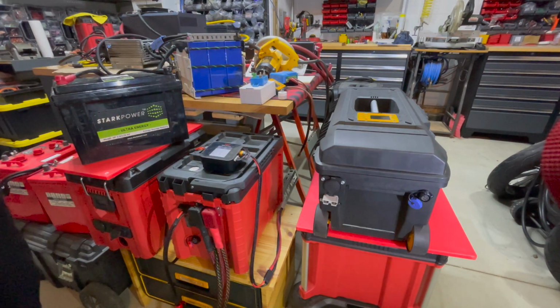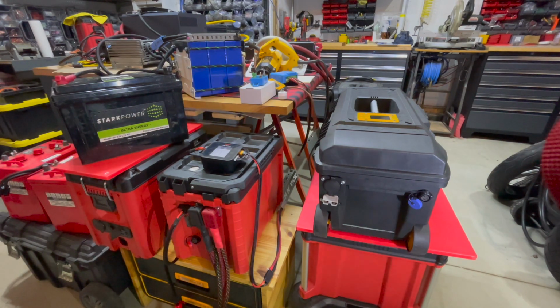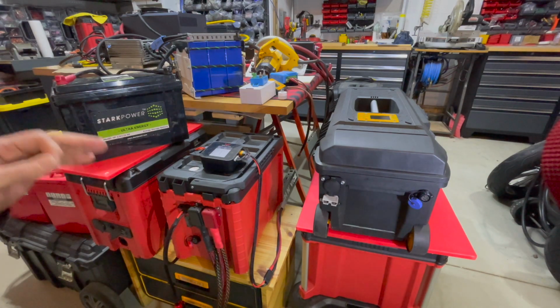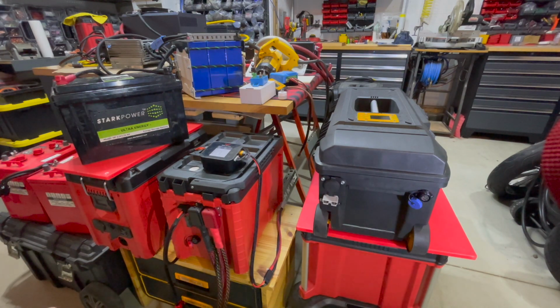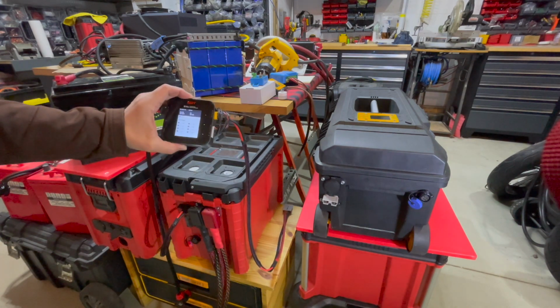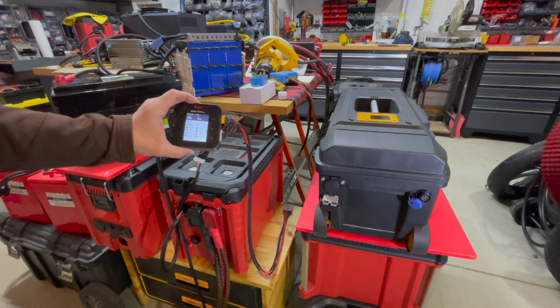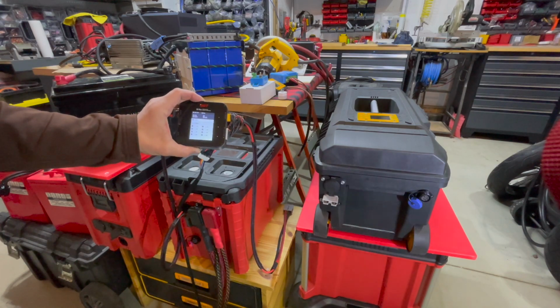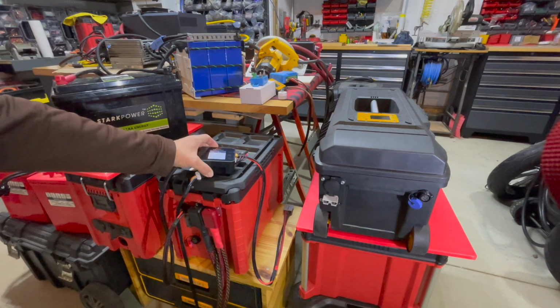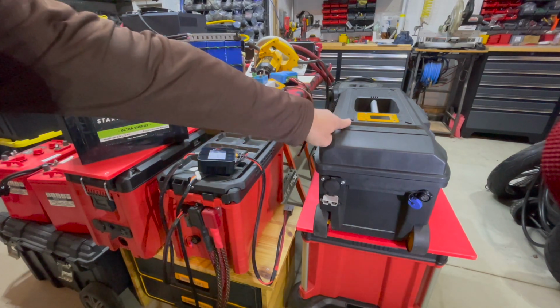It's only going to read the overall state of charge, which is like 11 to 15 volts. But we need to read each cell, ranging from 2.6 volts to 3.65, whether it's a 4 volt, 12 volt, 24, or 48 volt system - so 4, 8, or 16 cells. This is a charge controller, and you can read each cell, and decide how close to 3.65 you want to be. Now for this application, it has to be set lower than the other two BMSs in the battery.